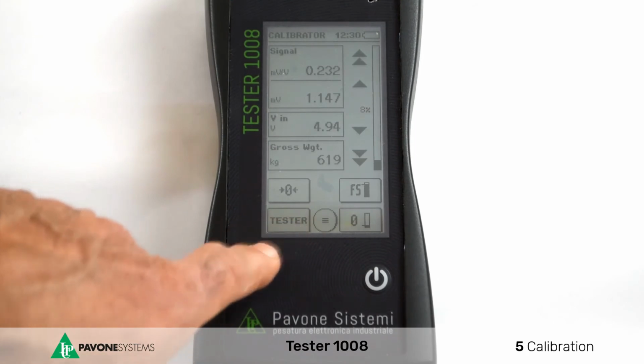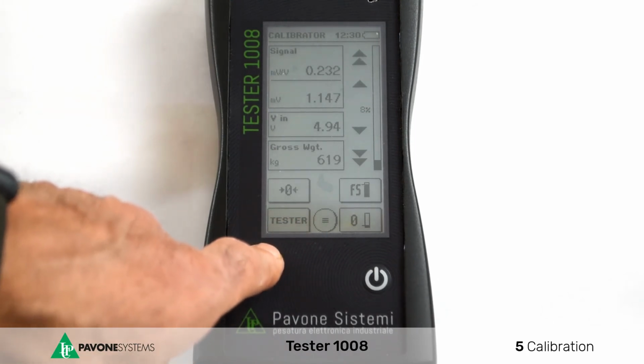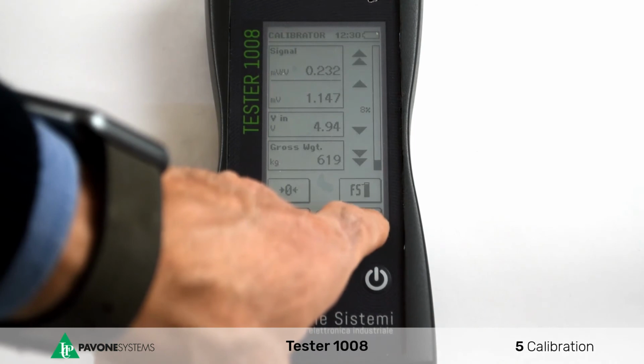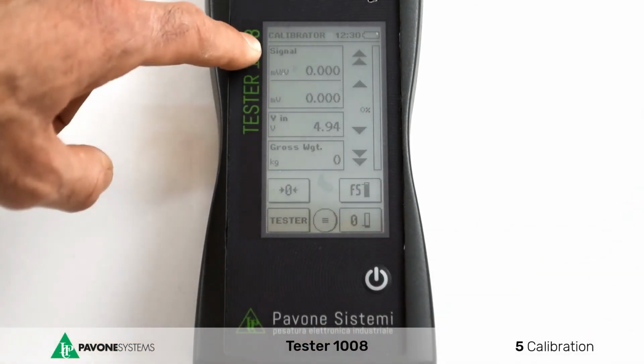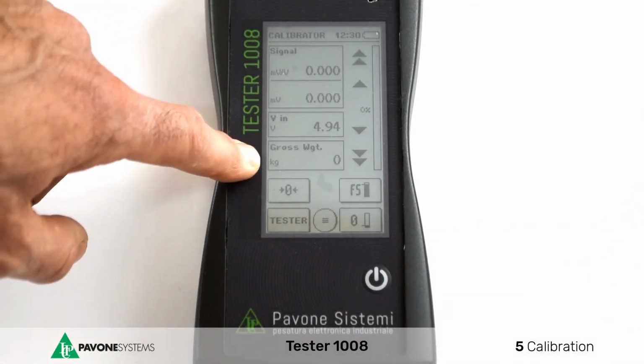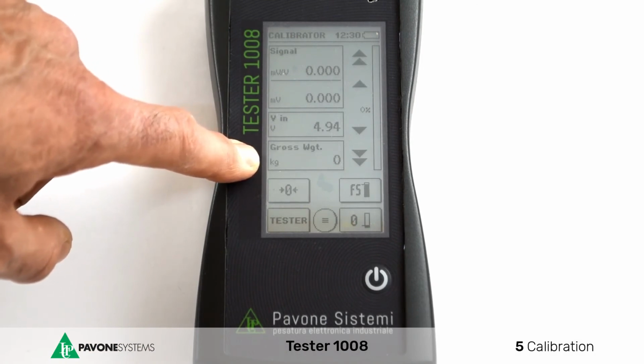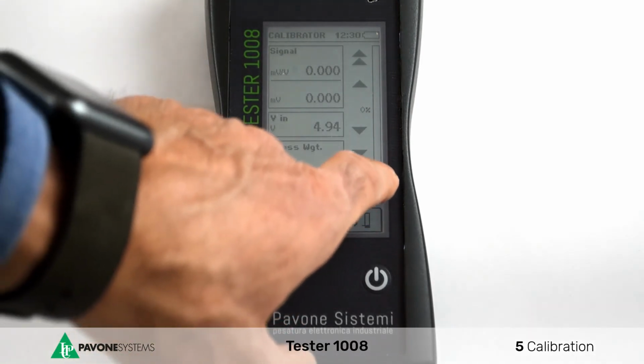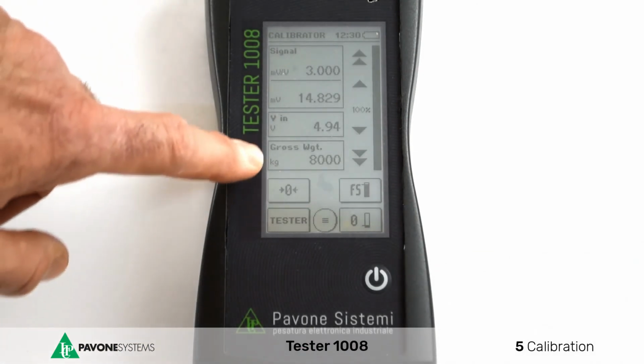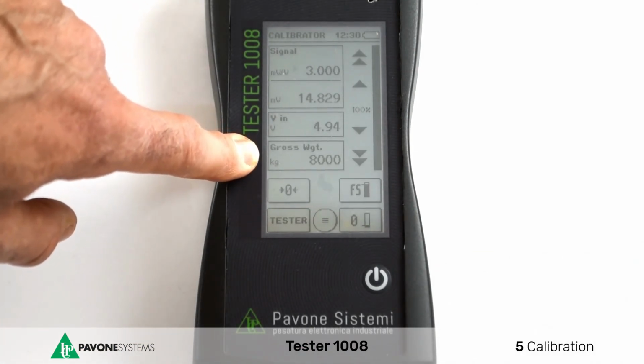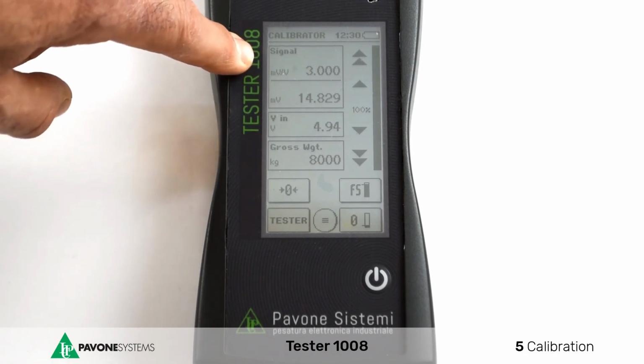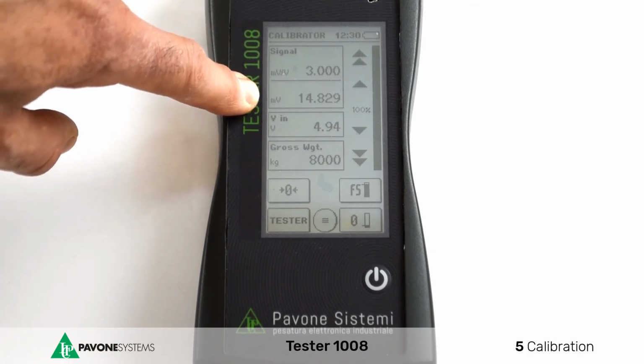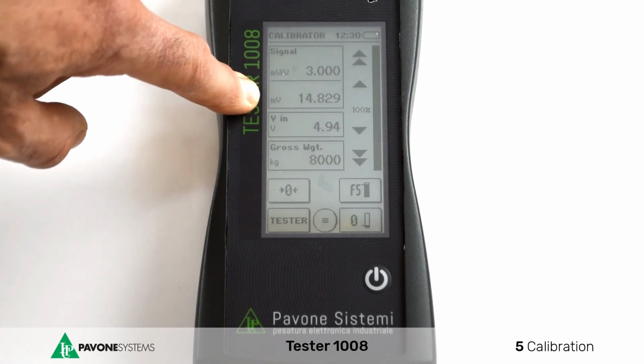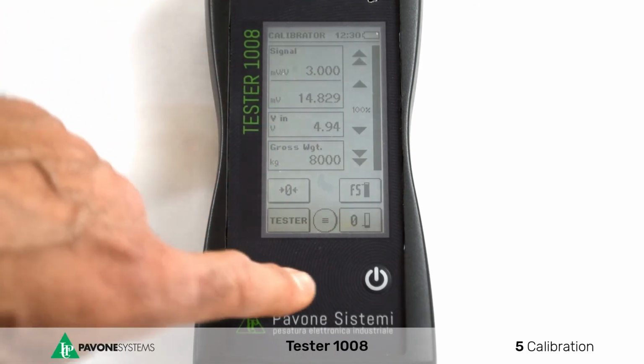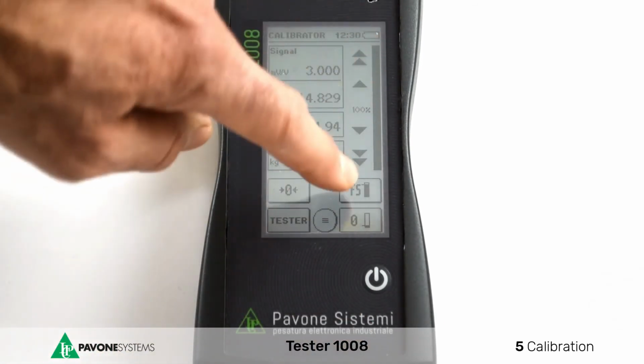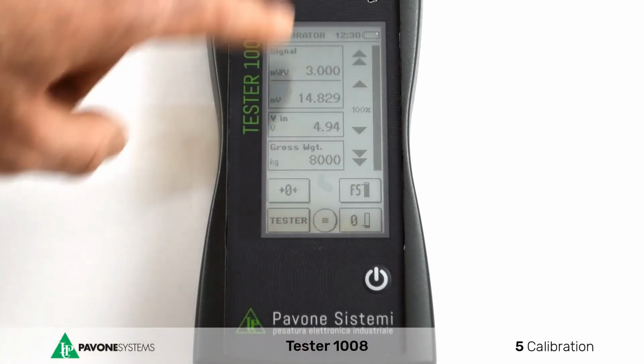The tester key allows you to go back to the first dimension and visualize the load cell's signal. The 0 key simulates 0 millivolt per volt and 0 kilograms. This means that no load is on the weighing system. With FS, you may simulate the full scale, in this case equal to 8,000 kilograms. The progress bar on the right side goes from 0 to 100%, and the fast or slow scrolling keys are used to change any simulation value.